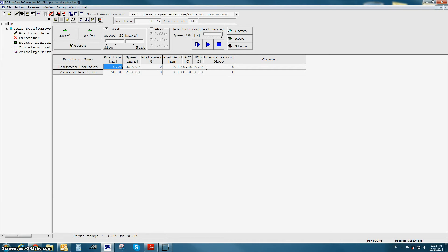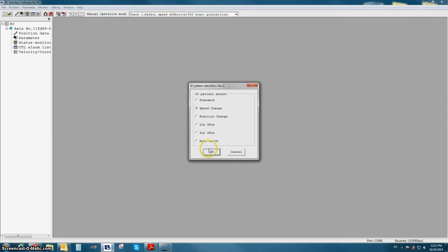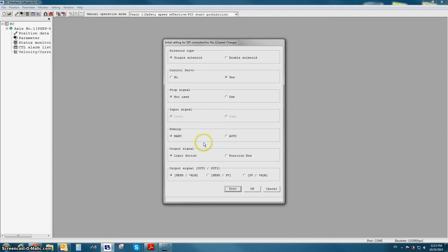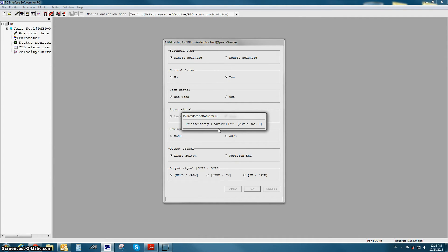I now want to change to PIO pattern one. I'm going back to Setting, Controller, Initial Setting for the SEP controller, entering the password 5119, and changing to speed change PIO pattern, otherwise referred to as PIO pattern number one. PIO pattern number one has all the same options as PIO pattern number zero, with an added signal for speed change mode. I'm going to press OK, restart the controller, and then reopen the position data screen to show what position data looks like for speed change mode.